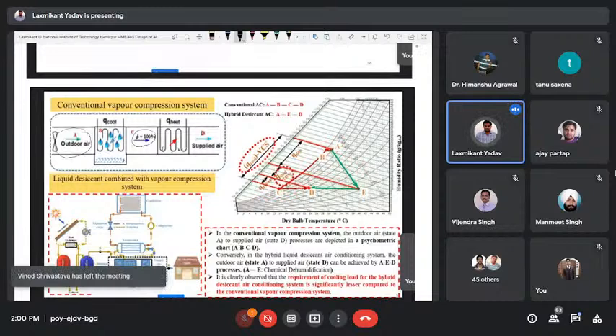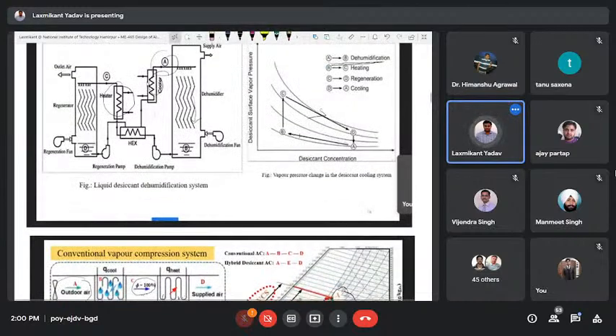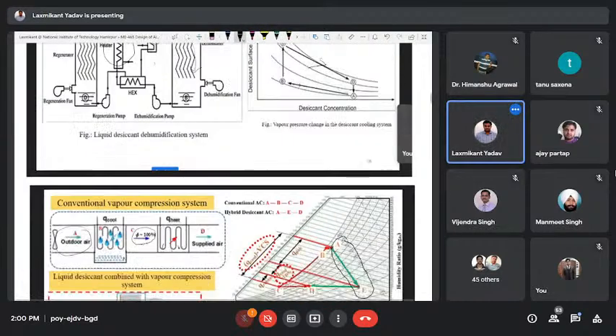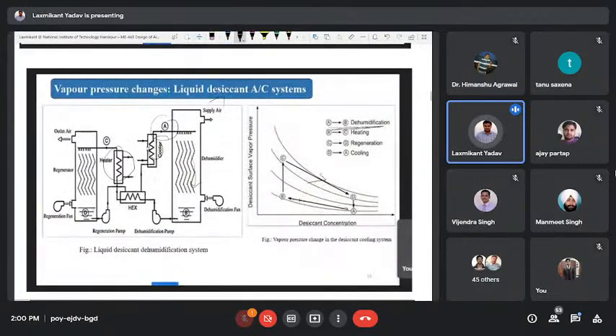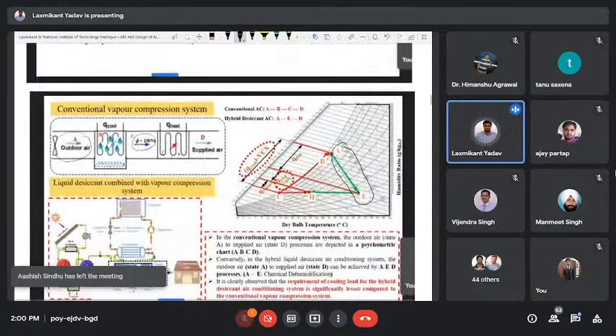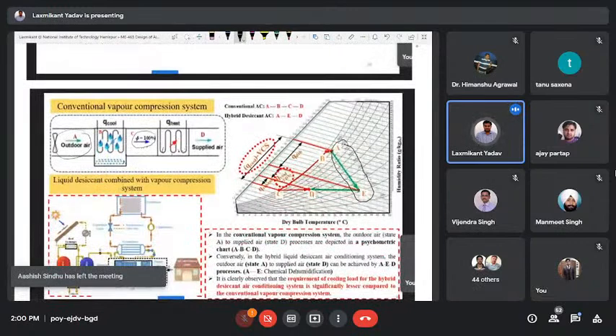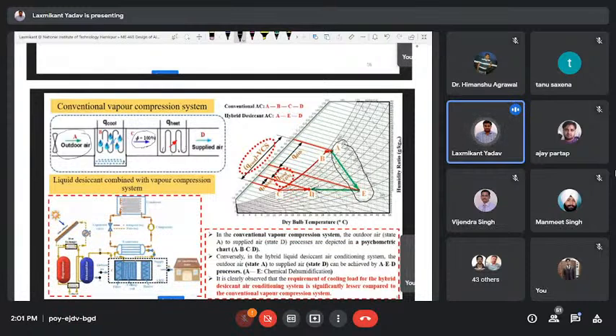However, this green color represents the liquid desiccant air conditioning. A to E represents the chemical dehumidification of air. So A to E is the dehumidification process. After that, this is the dry air. The dry air can then use either an indirect evaporative cooler, direct evaporative cooling, or sensible cooling to meet the room sensible heat factor line or supply condition. So the right side will consume less energy as compared to the left side.